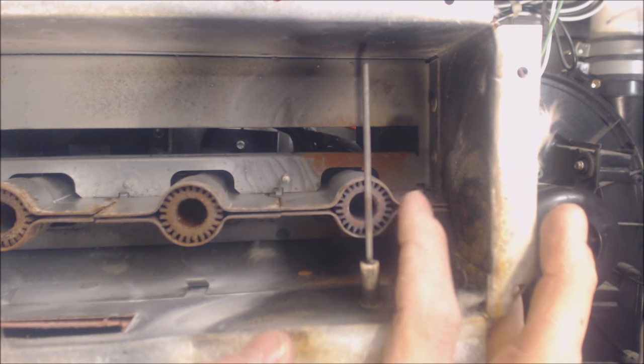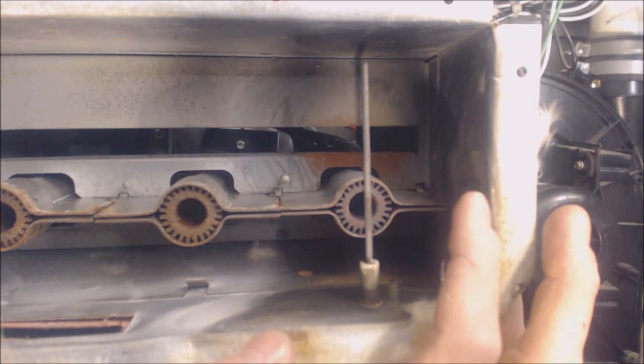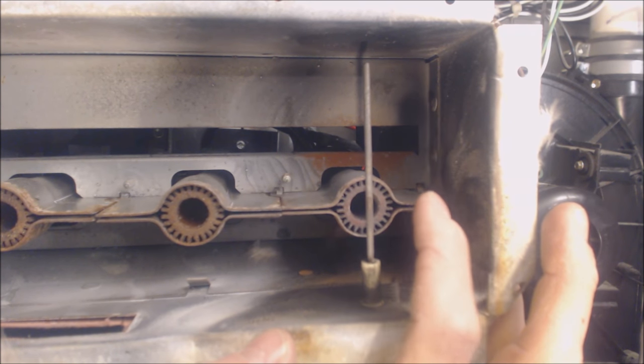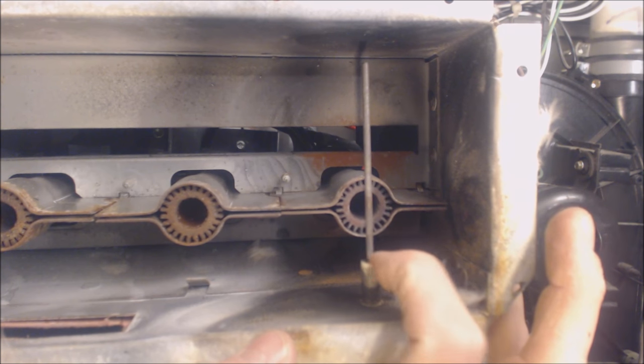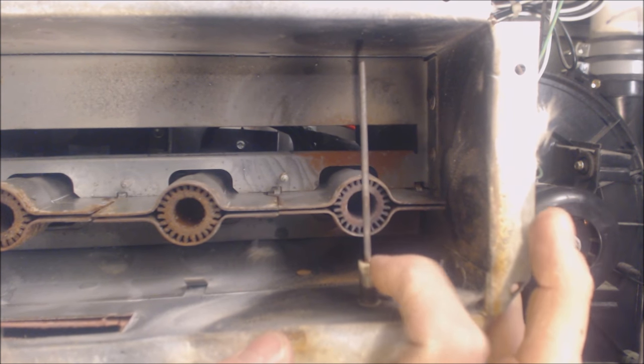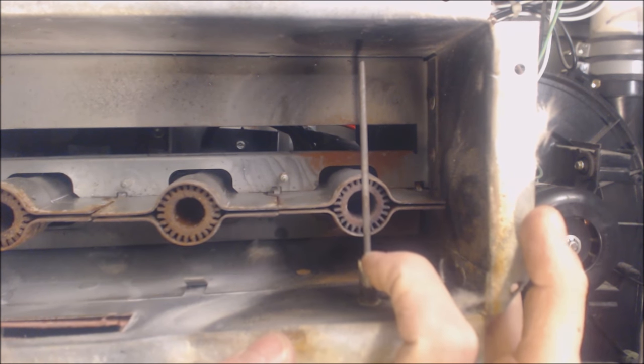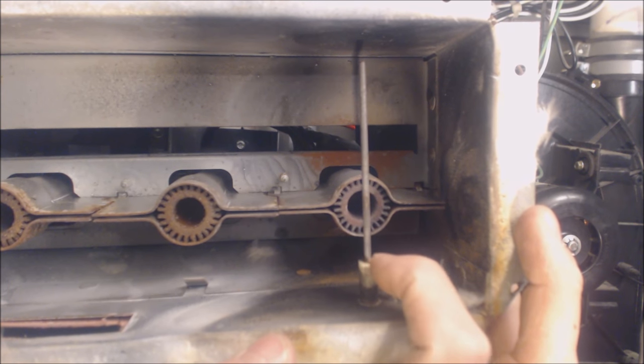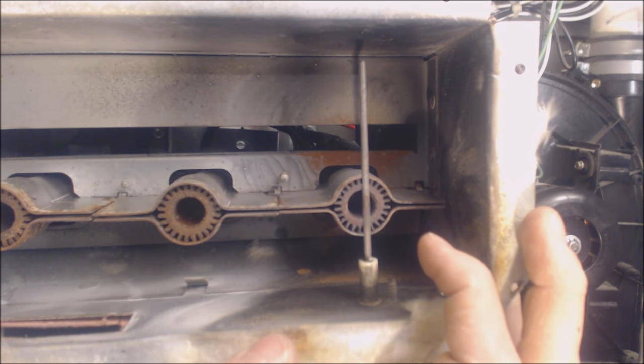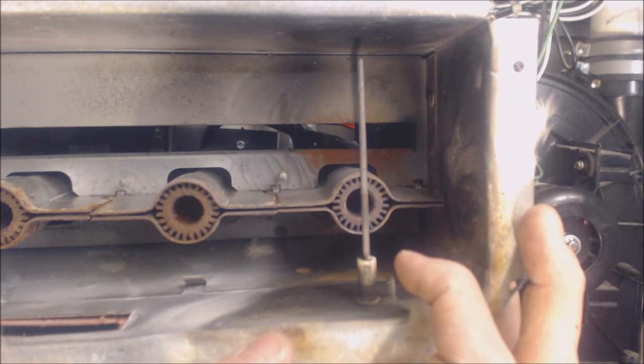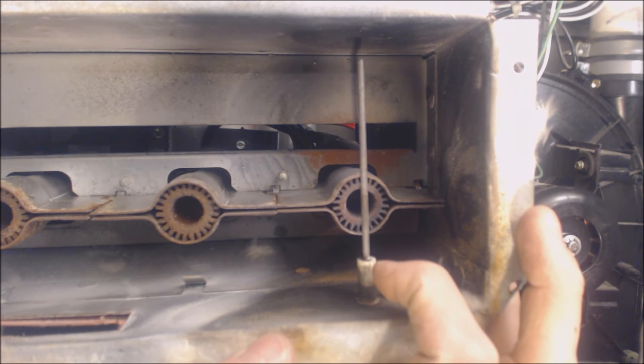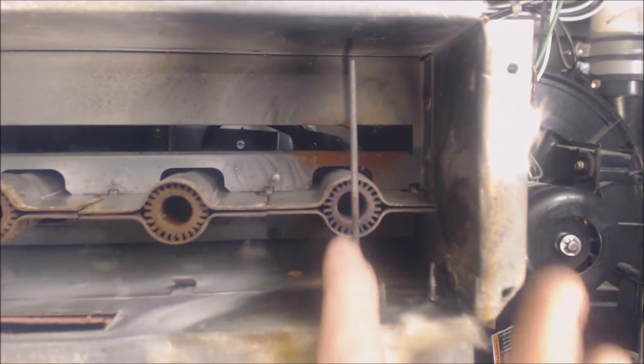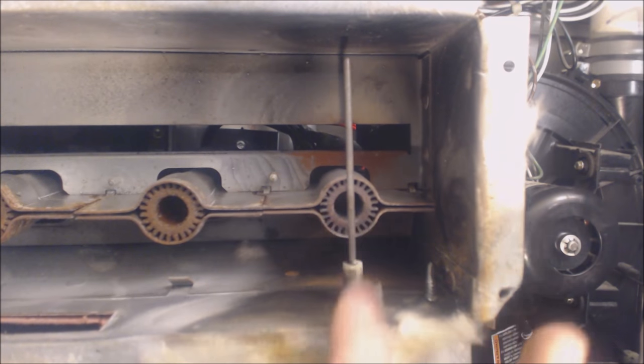DC amperage can be read through the grounding wire that's going to the module. And also what most people do is test right through the supply side AC voltage. You can actually put your multimeter in series and read the DC micro amps coming through the wire connecting to this flame sensor.